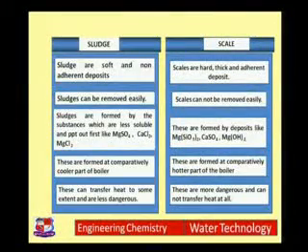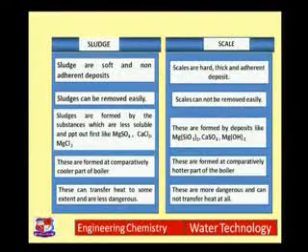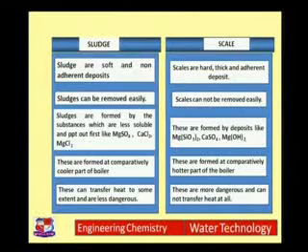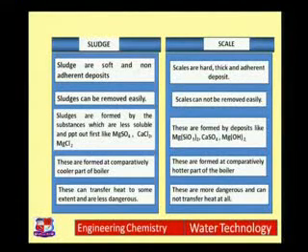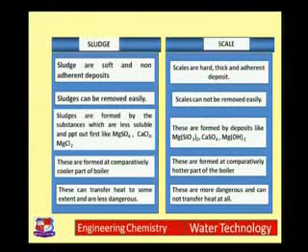Now let us talk about the basic differences between scale and sludge. Sludges are soft and non-adherent deposits — loose and slimy — that remain suspended in the boiler water. Scales, on the other hand, are hard, thick, and adherent deposits. Sludge can be removed easily by scraping with a brush or by blow-down operation, but scales cannot be removed easily. Some scales are so tough and thick that they may not even be removed by chisel and hammer.